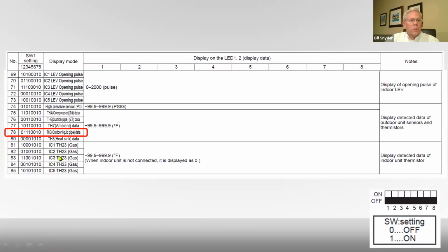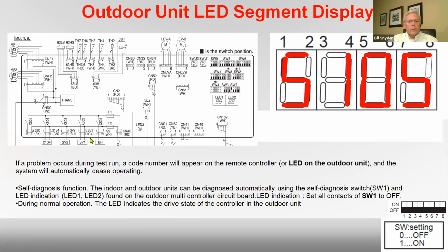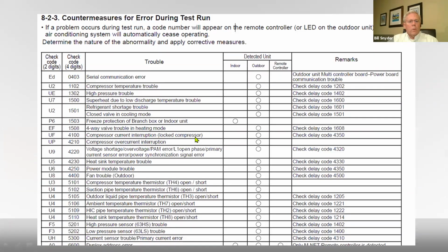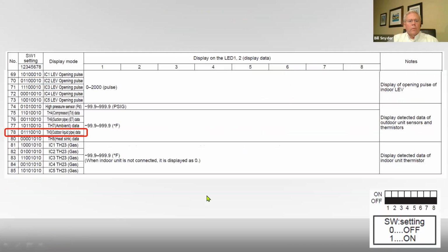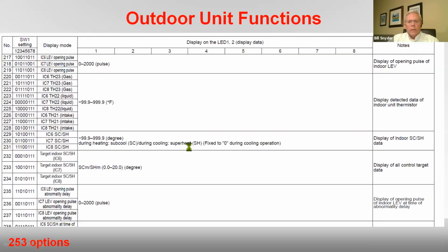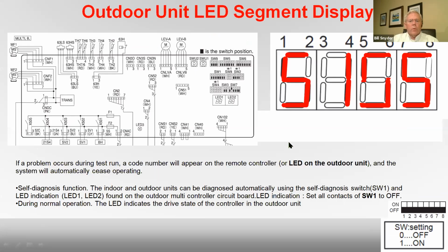In this case, we're going to go over here and look at number 78, which is TH3. Remember, that's what we said we had a problem with back here. This 5105 said TH3 was open or shorted. If we go to that switch, 0 is off, so we switch numbers 2, 3, and 4 to the on position, and we take the second from last one, number 7, and switch that on. This display here will now change and give you a reading.